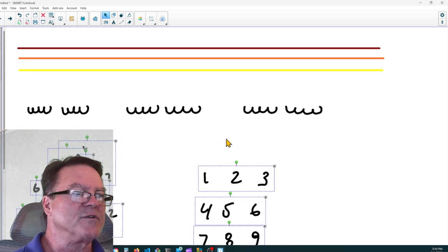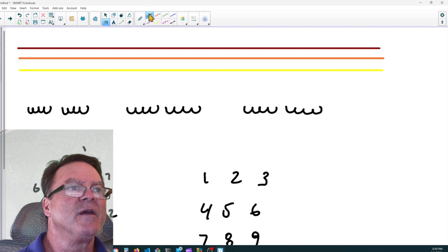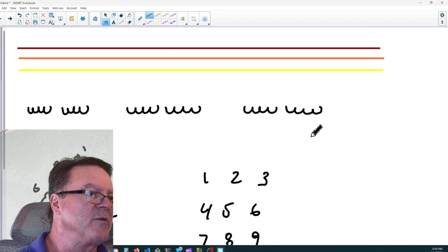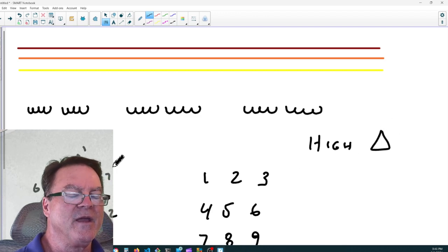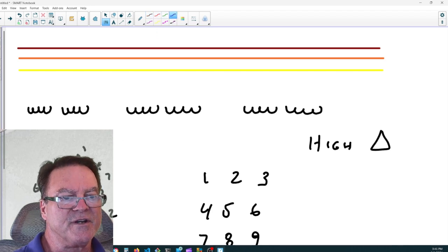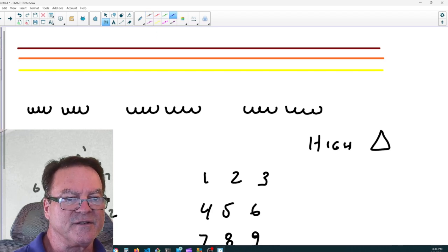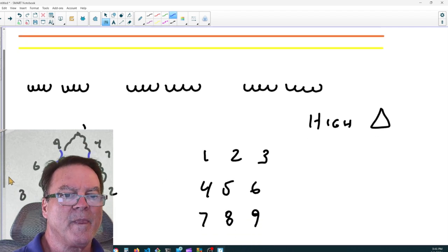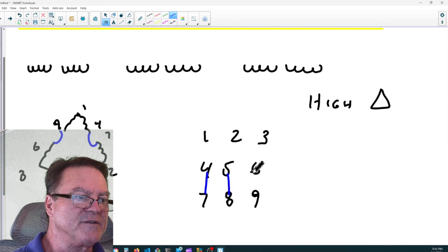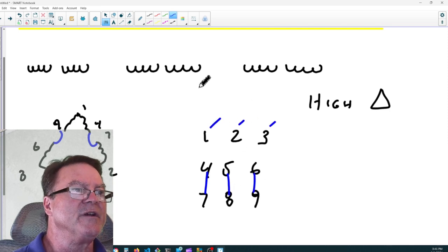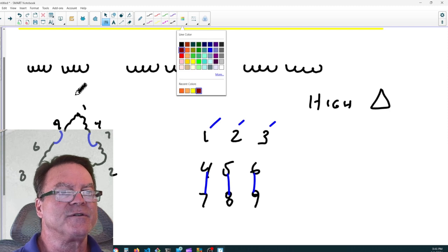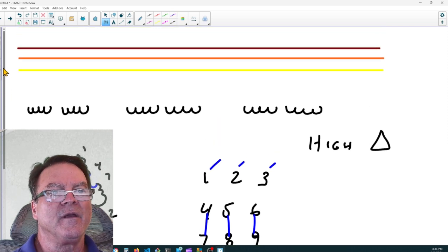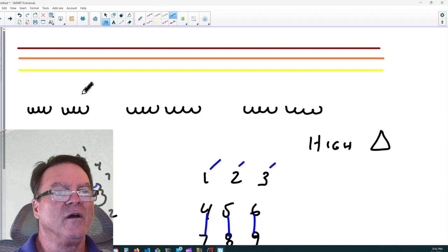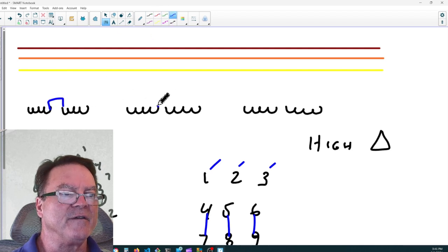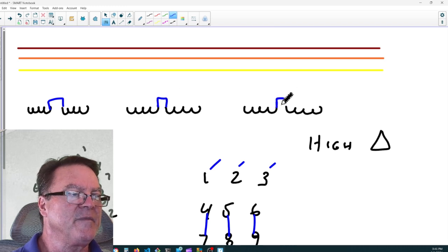So again, if we're talking about high voltage, 240, 480, we're going to hook it up 480. We're going to hook it up high delta. Again, we're going to go in series. We'll go 4 to 7, 5 to 8, 6 to 9. Here's 4 to 7, 5 to 8, 6 to 9. 1, 2, and 3 are our leads out. So here we're going to take 4 to 7, 5 to 8, and 6 to 9.